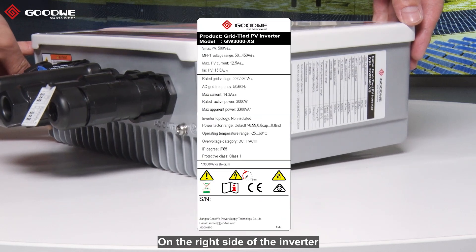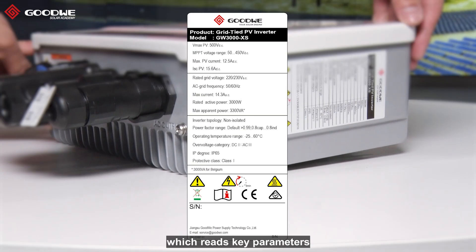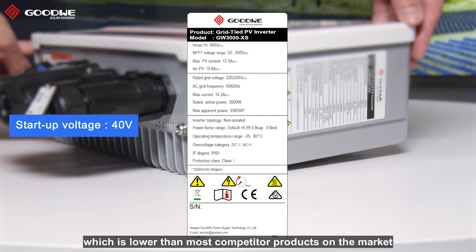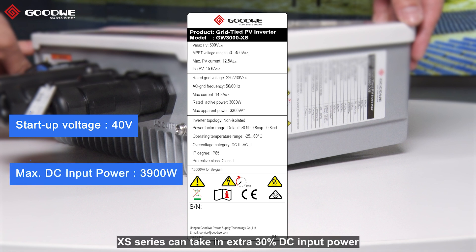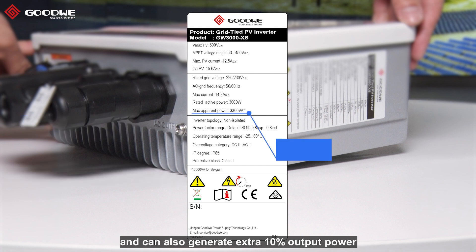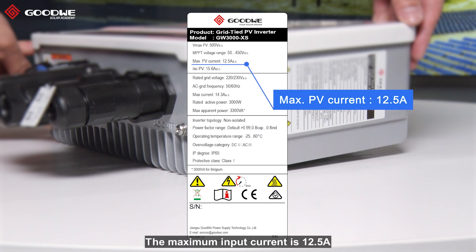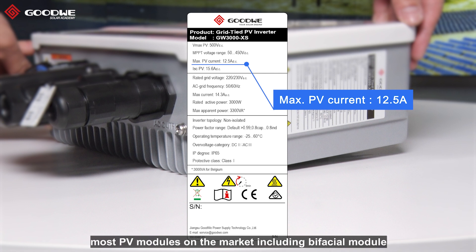On the right side of the inverter, there is a product label which lists key parameters. As we can see, the startup voltage is 40V, which is lower than most competitor products on the market and allows for longer operation time during the day. The XS series can take in an extra 30% DC input power and generate an extra 10% output power. The maximum input current is 12.5A, which makes the GoodWe XS series compatible with most PV modules on the market, including bi-facial modules.